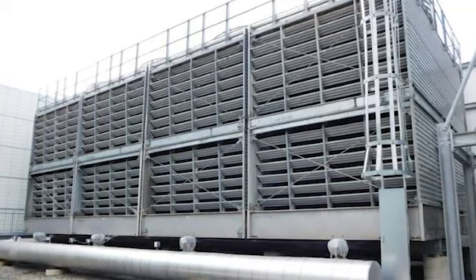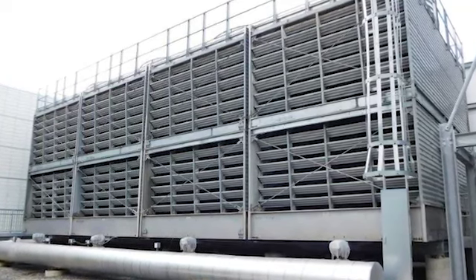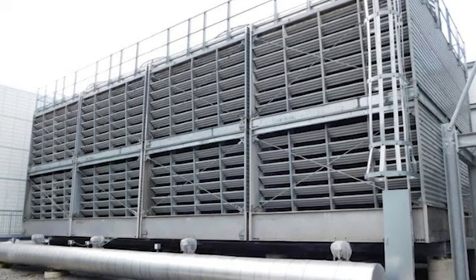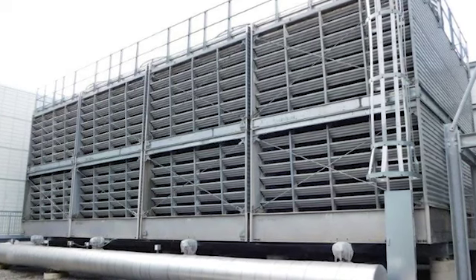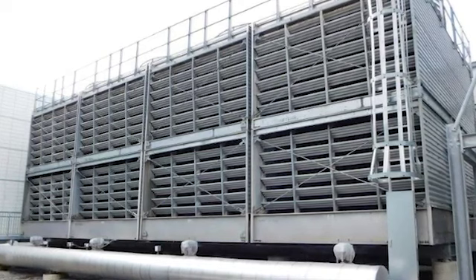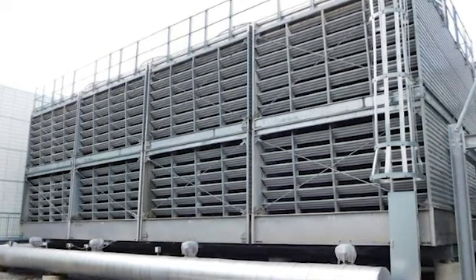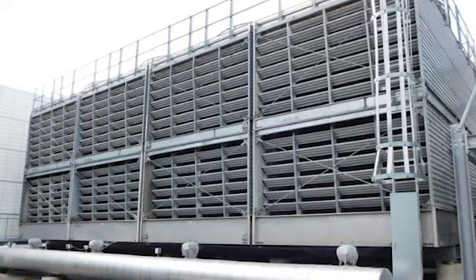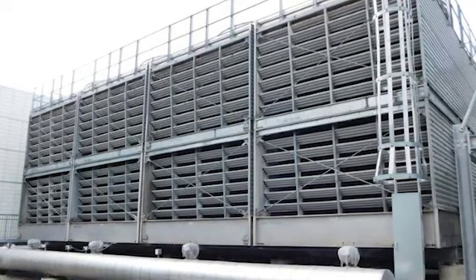One of the interesting things about having a thermal energy storage tank, and we'll show you that in a second, is that you're able to shut down and keep that tower super clean. We'll actually get in there with a pond vac and suck out the dirt. And it's been our experience that with a really clean cooling tower, when there's no mud or dirt inside, it's almost impossible to get Legionella in that tower.